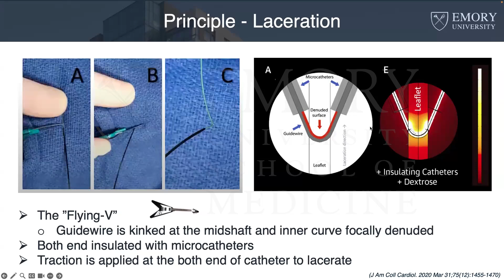And then both sides of the flying V are further insulated by a microcatheter to again avoid dispersal of current energy. And once this configuration is delivered to the target tissue, both ends of the catheter are pulled while applying radiofrequency to allow for the tissue laceration. So that's the basic physics of radiofrequency or transcatheter electrosurgery.